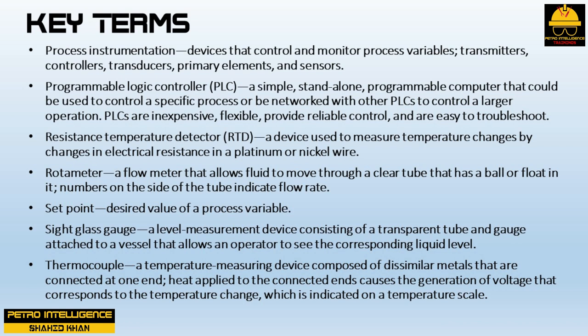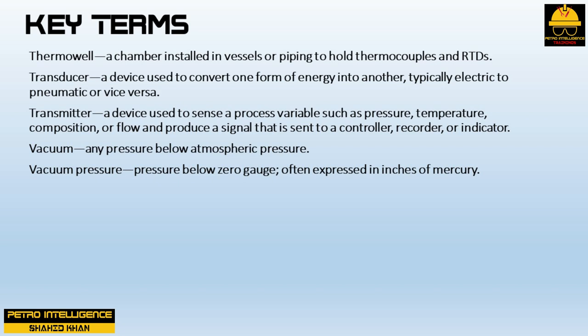A rotameter is a flow meter that allows fluid to move through a clear tube with a ball or float; numbers on the side indicate flow rate. A set point is the desired value of a process variable. A sight glass gauge is a level measurement device consisting of a transparent tube attached to a vessel that allows an operator to see the liquid level. A thermocouple is a temperature measuring device composed of dissimilar metals connected at one end; heat applied causes voltage generation corresponding to temperature. A thermowell is a chamber installed in vessels or piping to hold thermocouples and RTDs.